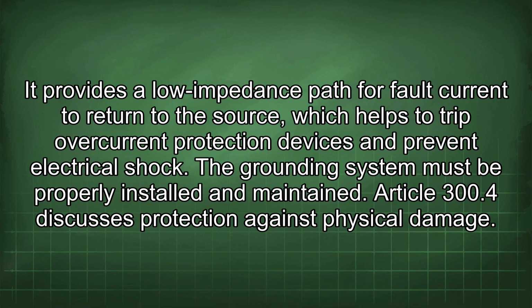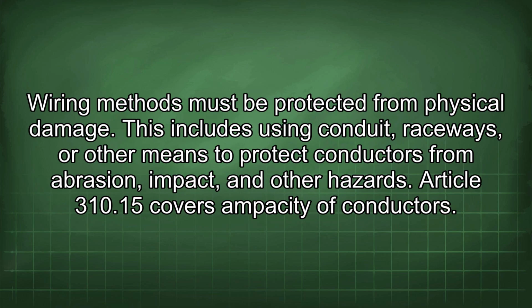Article 300.4 discusses protection against physical damage. Wiring methods must be protected from physical damage. This includes using conduit, raceways, or other means to protect conductors from abrasion, impact, and other hazards.